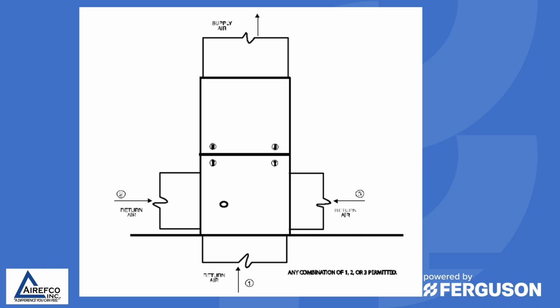Make sure that you're aware of any notes that might be in the installation guide, such as this, that on an upflow configuration furnace, this manufacturer states that any combination of 1, 2, or 3 is permitted. So you must have either a left or right return along with the bottom of the furnace. So make sure you double check the installation instructions that you're doing it correctly.